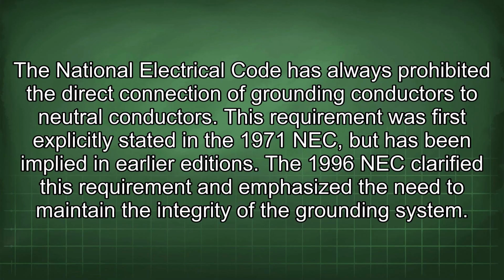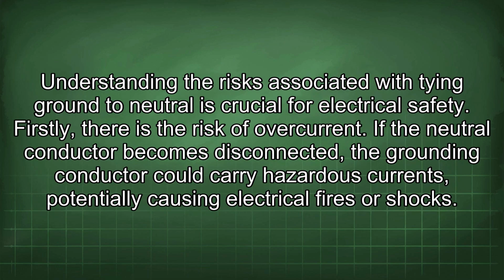The National Electrical Code has always prohibited the direct connection of grounding conductors to neutral conductors. This requirement was first explicitly stated in the 1971 NEC, but has been implied in earlier editions. The 1996 NEC clarified this requirement and emphasized the need to maintain the integrity of the grounding system. Understanding the risks associated with tying ground to neutral is crucial for electrical safety.